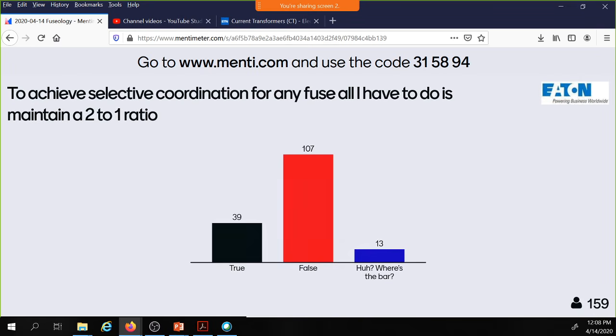You're looking good so far. I mean, these are great. Look how we have 107 say false, and if they're right, then we've got 108 people that think they're right, which is good. And we only have 39. So to achieve selective coordination for any fuse, all I have to do is maintain a 2-to-1 ratio. And the right answer to this is false, because some fuses may need a higher ratio than 2-to-1.